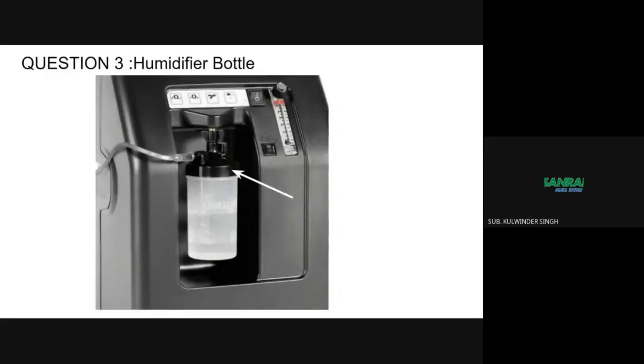The humidifier bottle is used to moisturize oxygen, decreasing dryness during delivery to the patient. It provides comfort and prevents drying of the nose, mouth, lungs, and respiratory membranes. It is attached to the patient outlet fitting of the concentrator, and the oxygen passes through distilled water in the humidifier bottle before reaching the patient.